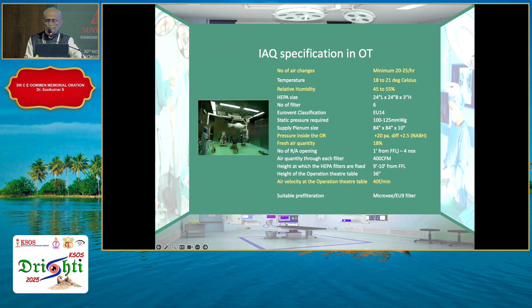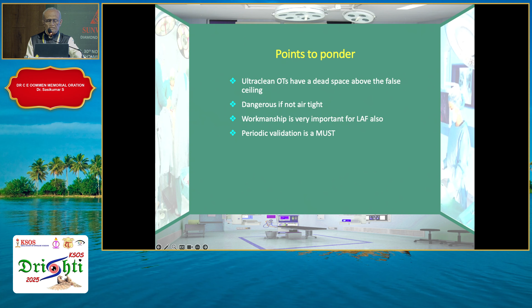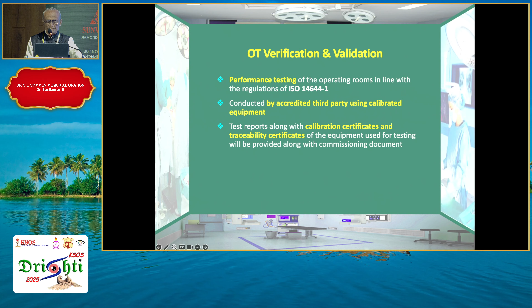Contaminants from that space can leak into the OR if there is a leak, or if there is a gap in the box. Hence, good workmanship and periodic validation is a must. OT validation is usually done by a third party in line with the regulations of ISO 14644-1. OT has to maintain the test reports and the calibration certificates.